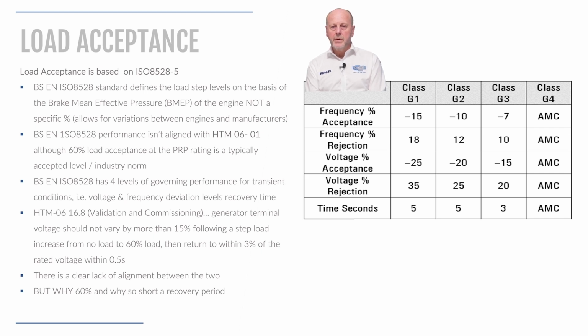As you can see, there is no direct link in this area between HTM-06 and ISO 8528, with its recognition of different levels of performance between engine manufacturers or to the 4 governing categories set out in the ISO standard. Why is this the case when this is one of the most critical aspects of performance? We find some level of alignment between the two when we look at Category 3, but a recovery time of 5 seconds as per G2 level of performance. So slightly longer than the engine standard, but still achievable.